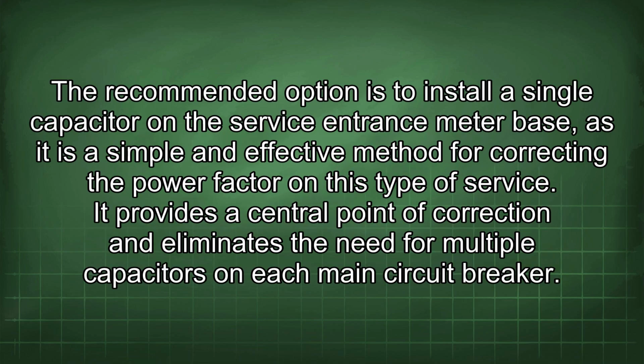The recommended option is to install a single capacitor on the service entrance meter base, as it is a simple and effective method for correcting the power factor on this type of service. It provides a central point of correction and eliminates the need for multiple capacitors on each main circuit breaker.